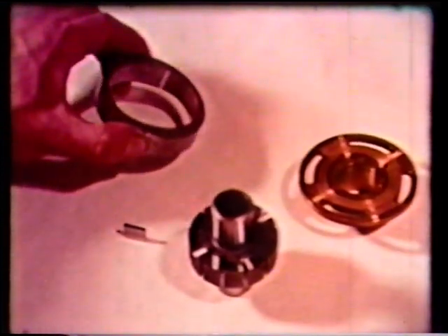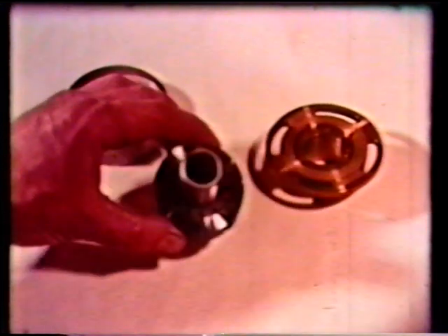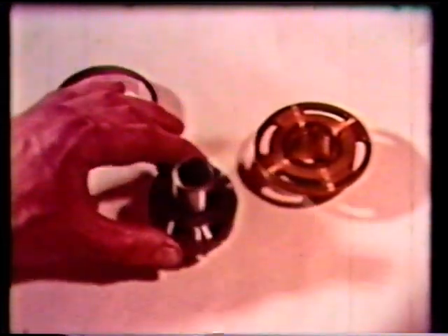Vapor cavities in the fluid have impaired effective lubrication, the ring surface is badly worn, the vanes are damaged, the vane grooves in the rotor are worn, and the bushings show wear in the area of contact with rotor and vanes. Severe wear steps are found on the ring surface in the immediate area of each outlet port. The surface between inlet and outlet ports is damaged by scuffing wear marks.